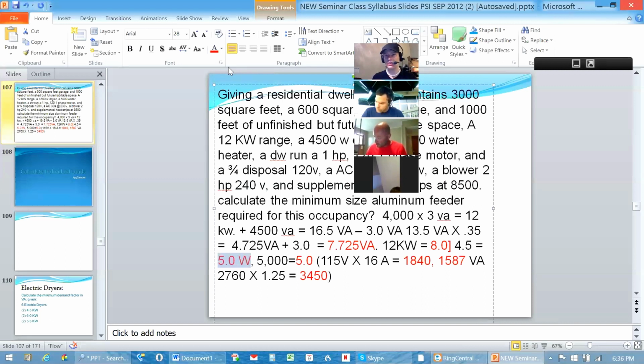So that AC unit at 30 amps at 230 volts, 30 amps times 230 volts would give us a value of 6,900 VA. The heat strips at 8,500 are going to trump that. So we're going to just basically forget all about the air conditioning, and we're going to calculate the 8,500 at 100% for the heat. So omit AC, and 100% of the heat would be plus 8,500, 8.5 kW. Okay, or kVA.